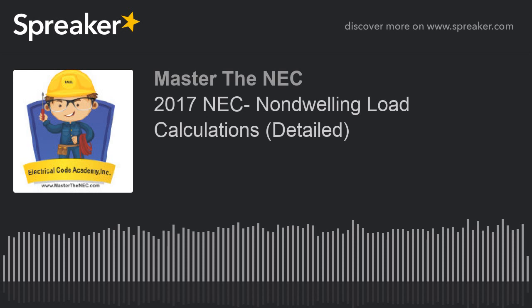Another thing to remember is, in no case can the grounded conductor, in our case neutral, be smaller than what's specified in 250.24(C)(1), which ultimately is going to send me to 250.102(C)(1). It can't be smaller than that, but it could be larger than those tables based on having to do a calculation. So you're going to take the larger of the two, but it can't be any smaller than the values that we calculate in 250.102(C)(1) based on the size of the service conductors, for example. That's what we're going to use to dictate it.